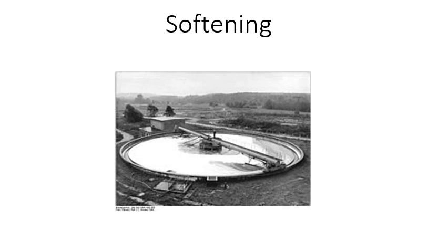So the lime softening process, this all happens simultaneously. Step 1, add water to unslaked quicklime, CaO. This produces hydrated lime, Ca(OH)2, or slaked lime, and heat plus grit. Step 2 is to meet the carbon dioxide demand.